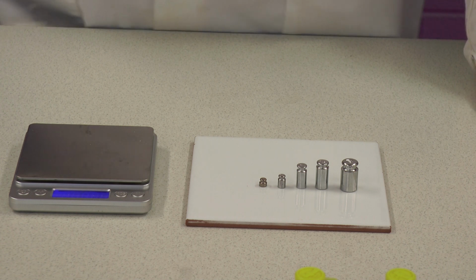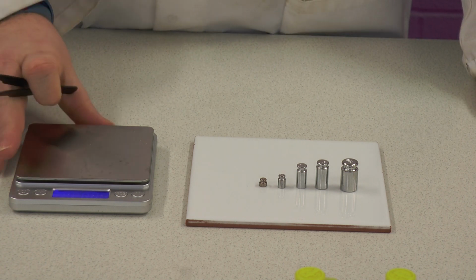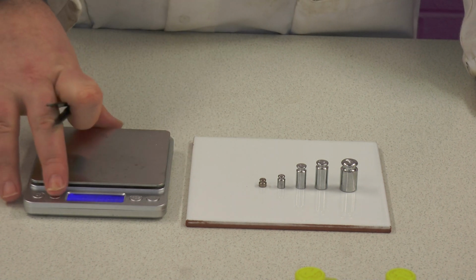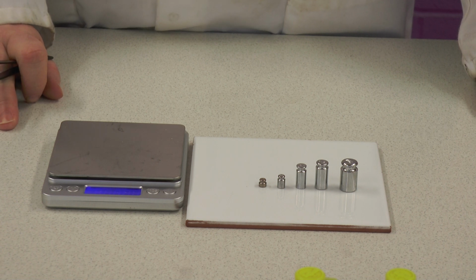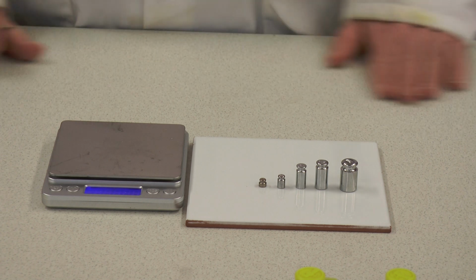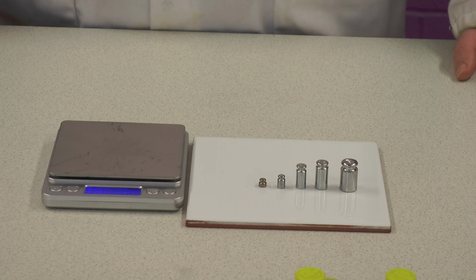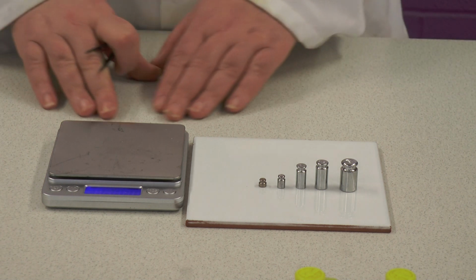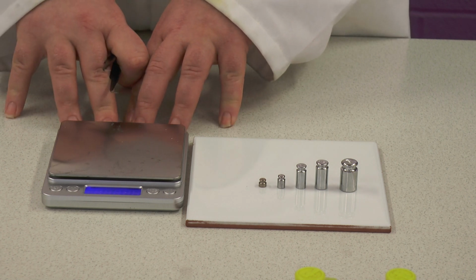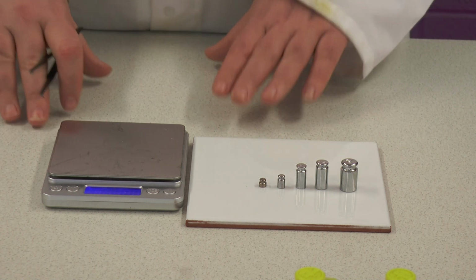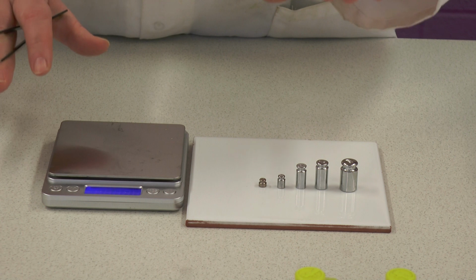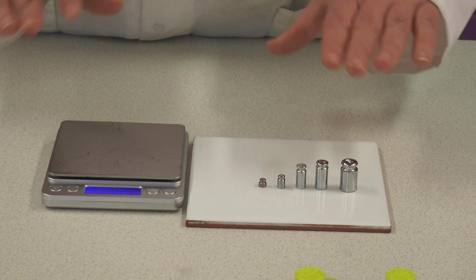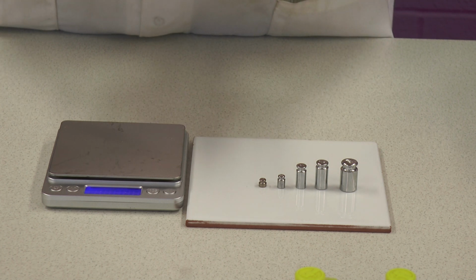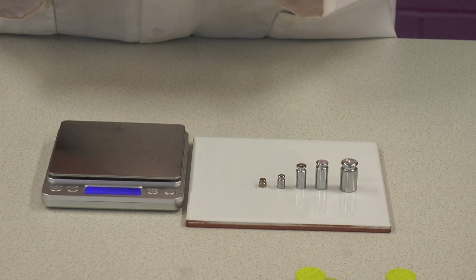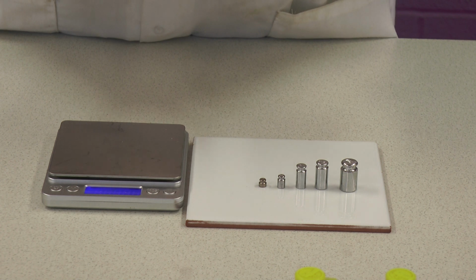The other way to do it is to create your own calibration graph. Now this would be used for scales that don't have digital calibration or for analog scales, and this would basically involve zeroing the balance, making sure that it's on a level, stable surface, because any motion or vibration will affect the readings that you get. On some of our balances, particularly our more advanced balances, you'll find that they have a built-in spirit level which will enable you to make sure that the balance is completely level. If the balance isn't completely level, there'll be an unevenness in how it weighs and how the sensors within the balance pick up that weight, and therefore you will not get a true mass of your substance or whatever you're weighing. So it's important that it's on a level, stable surface.